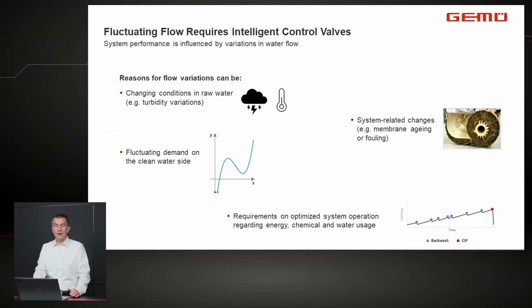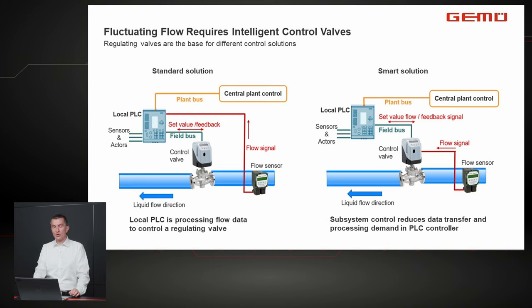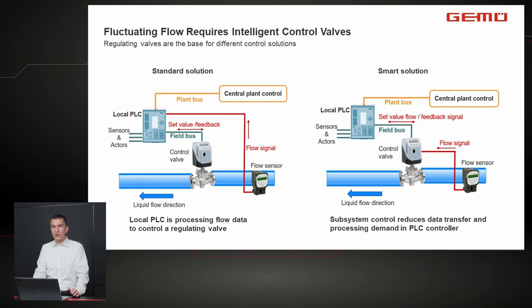The standard solution for flow adjustment is: a flow sensor sends a signal to the local PLC, which is connected to a central plant control system, which then instructs the control valve — via fieldbus or similar — to increase or decrease flow. A smarter solution sends the signal directly to the control valve, reducing data transfer. This is very useful for large plants, allowing a closed, independent control loop and reducing the data stream.